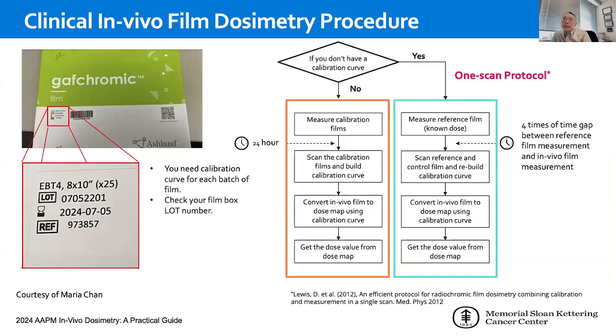Here's a sample of a clinical in-vivo film dosimetry procedure that we implemented in our institution. As you can see, it is a pretty complex process that we just described. So having a clear process is very helpful in the clinic. For example, we clearly identify that you need to have the same batch, which is typically shown on the box of the film being used. So if we don't have a calibration curve, we'll want to generate a curve, and then we'll scan it after 24 hours, and then we'll build the calibration curve, and then we'll convert the film to dose using the calibration curve. However, if we already have a calibration curve, we will use a one-scan scanning procedure or protocol.